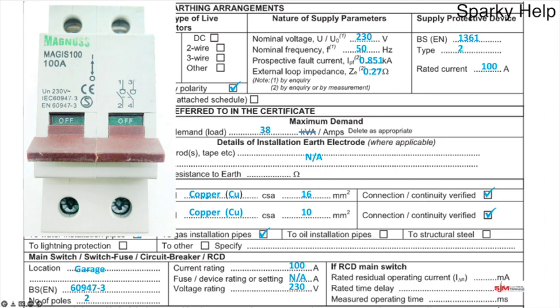If it happens to be an RCD, obviously you would then test it with an RCD tester to see how many milliseconds it disconnected in the most onerous of the times that you then check it. In our case though, we don't have one, so they are NA. Next bit down to the bottom of the page, it says schedules are attached. And these are the two documents that get handed in with an electrical installation. They are the schedule of inspections and the schedule of test results. And basically you have to insert in here how many of each go in.